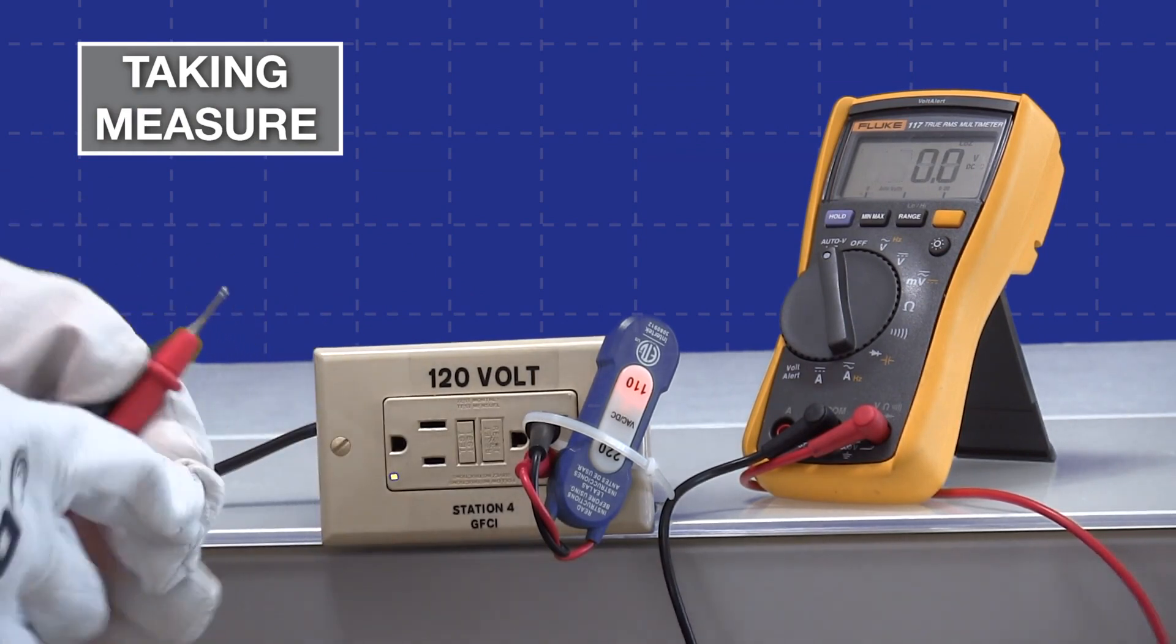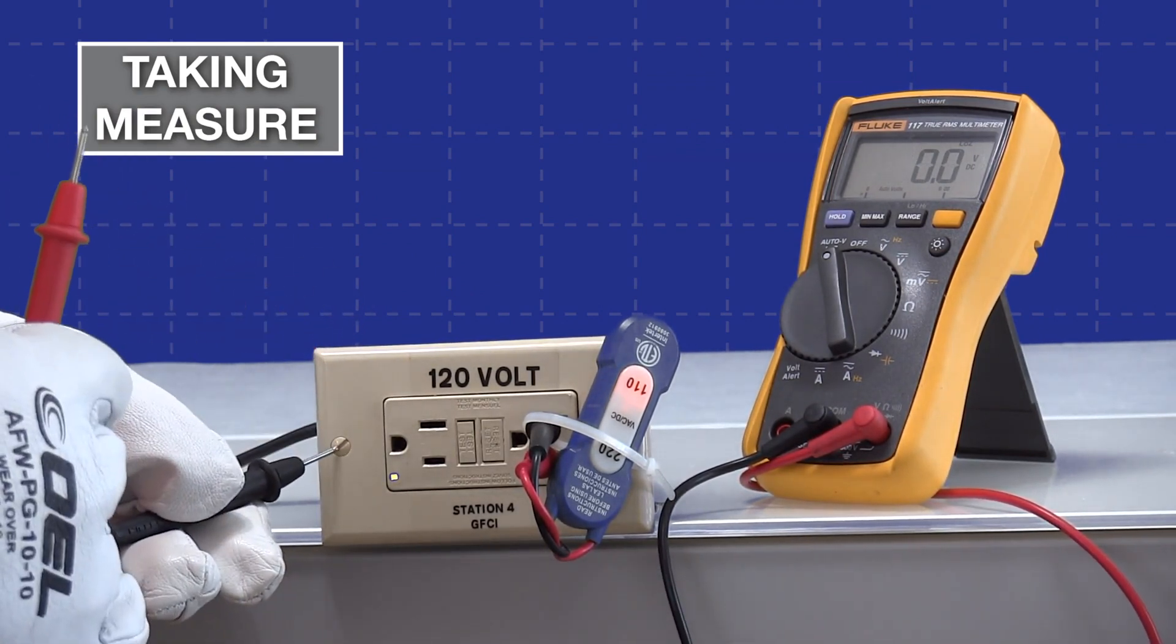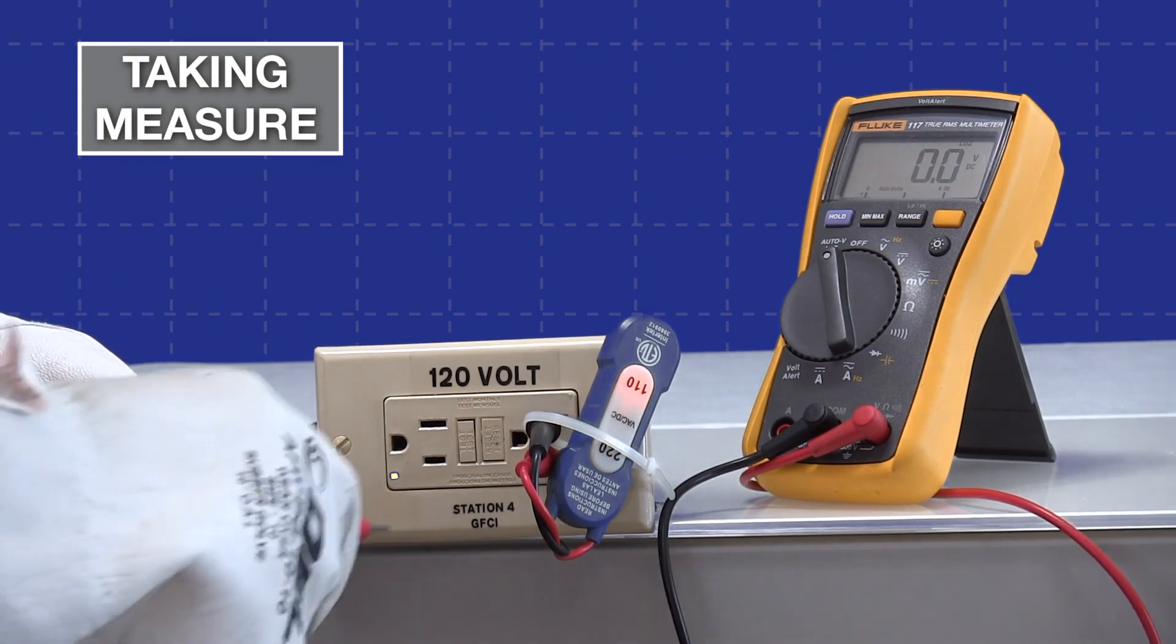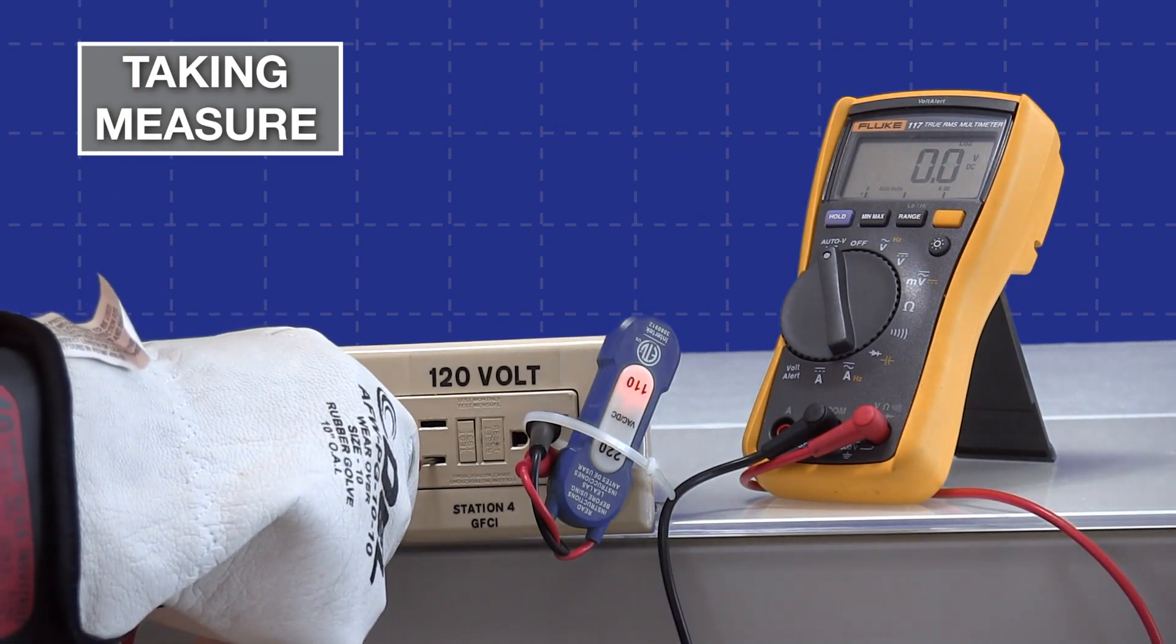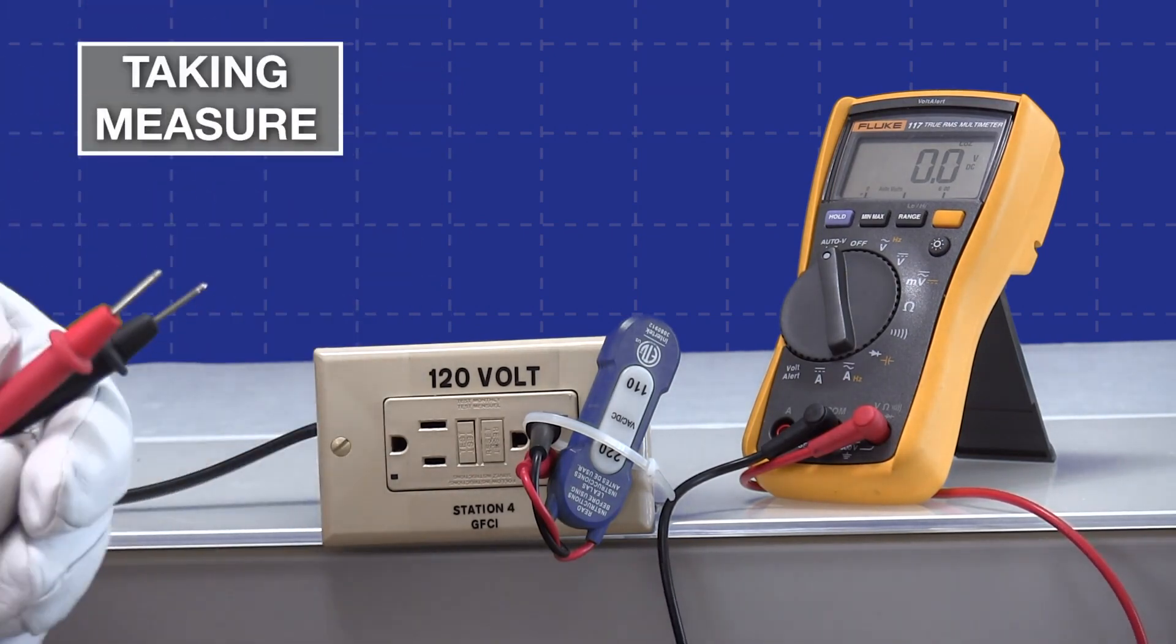Now we'll try to measure to the ground again. I'll put the probe on ground first, and then go to the ungrounded conductor, and you'll notice the light went out. We tripped the circuit. That's because the low impedance drew enough current, it impacted the circuit, and tripped it out. That's exactly what meter loading is.